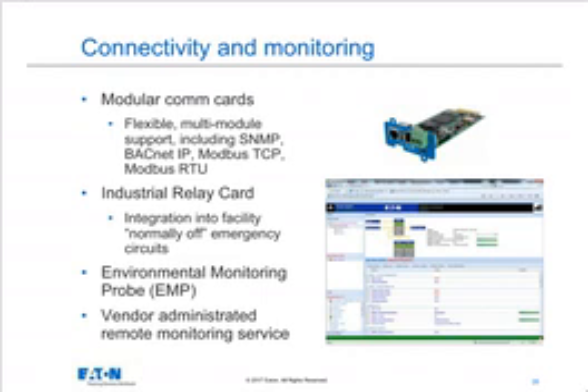If my building uses Modbus for most of its infrastructure monitoring, the UPS can provide that kind of connectivity or protocol. If they'd rather use BACnet, or if it's a data center and they'd rather use SNMP, for example, the answer is yes to all of those. From most UPS vendors, they can communicate using whatever protocol the client chooses.